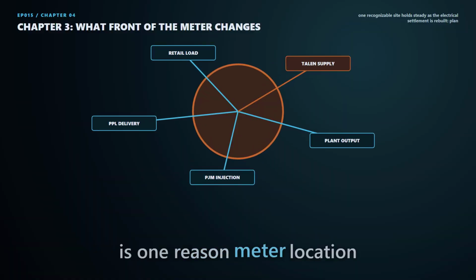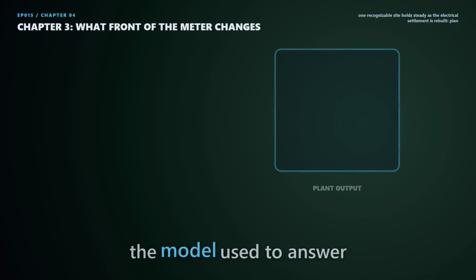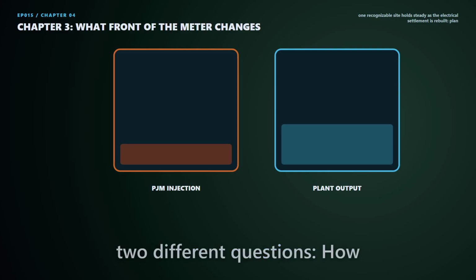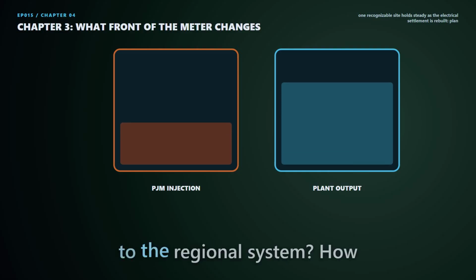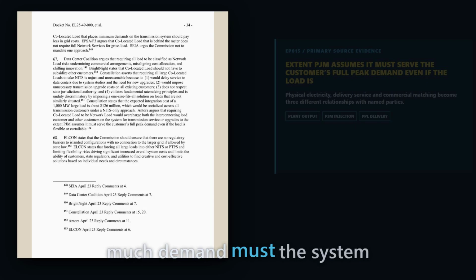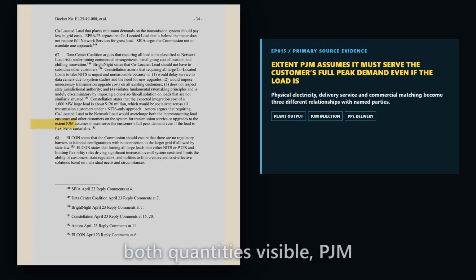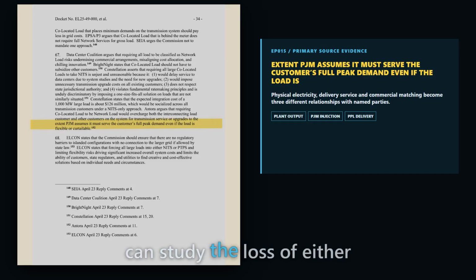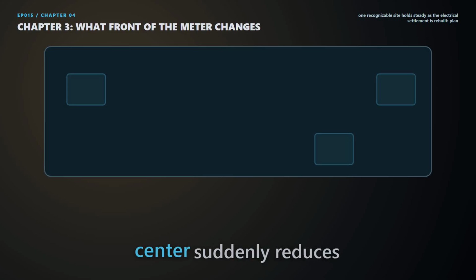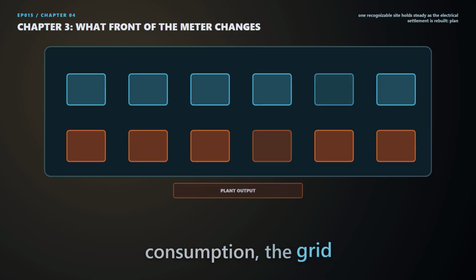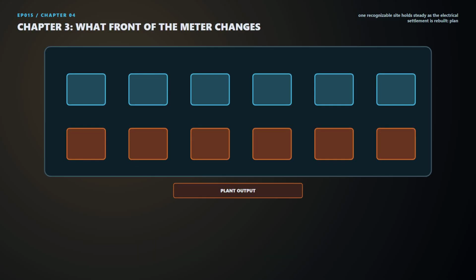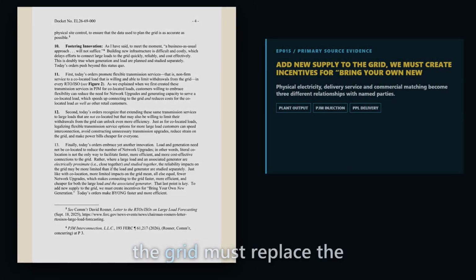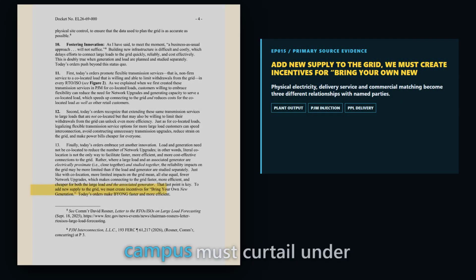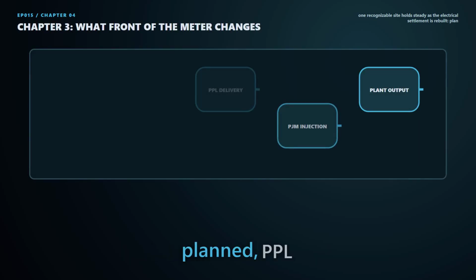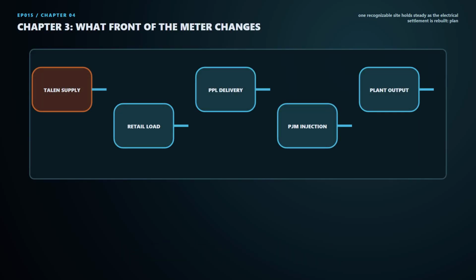That is one reason meter location matters. It changes the model used to answer two different questions. How much power is the plant offering to the regional system? How much demand must the system be ready to serve? With both quantities visible, PJM can study the loss of either side. If the data center suddenly reduces consumption, the grid absorbs the generation surplus. If a nuclear unit trips, the grid must replace the missing supply, or the campus must curtail under its service agreement. If the campus ramps faster than planned, PPL and PJM see the demand against the network.